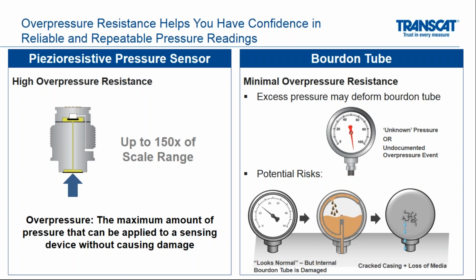With a wireless pressure gauge, it has up to 150 times what the scale range is. So again, an example here, if the scale range was 1 PSI, that would mean you'd have 150 PSI that you'd have to get to before you'd have irreversible damage where you can no longer rely on that pressure gauge's integrity. What this allows you to do is put this kind of technology in pretty demanding applications, knowing that any sort of pressure spikes are not necessarily going to damage the sensor.